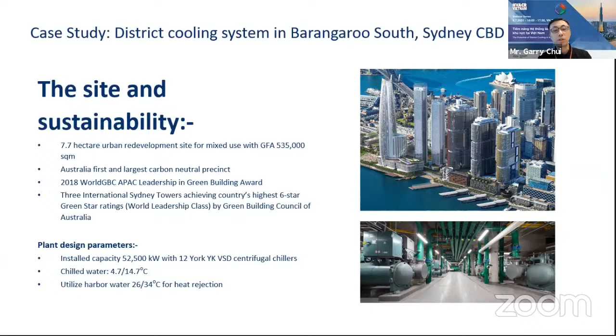So this redevelopment project has been using district cooling systems. At the bottom you see the major parameters. It's using typical, large tonnage centrifugal chillers with an installed capacity of 52,000 kilowatt, and with the chill water temperature. One thing that is special is that the site is located next to the Darling Harbour front. So instead of using a freshwater cooling tower, this site is applying direct seawater for the heat rejection. Next slide, please.